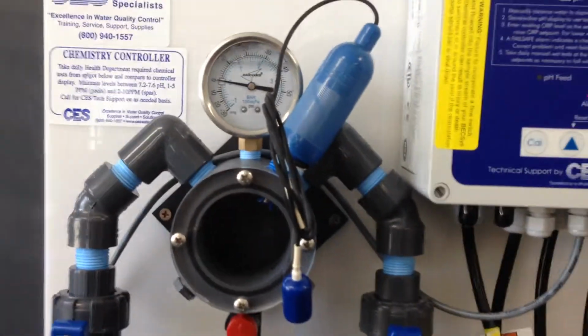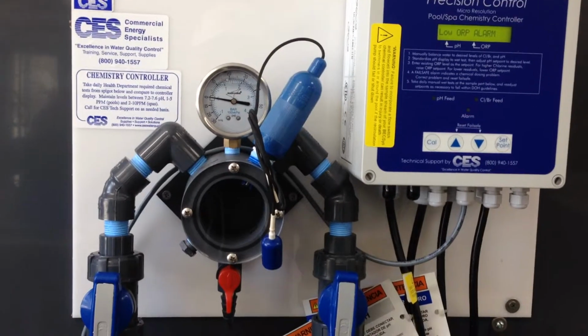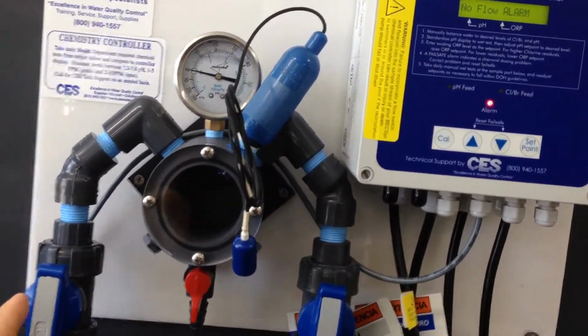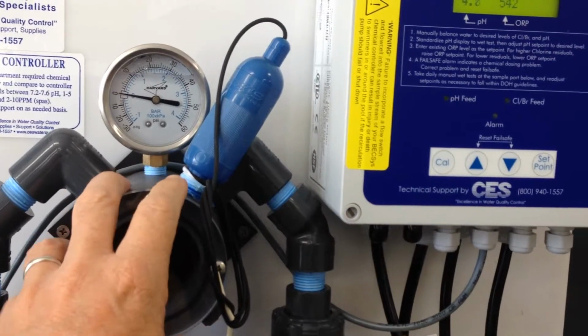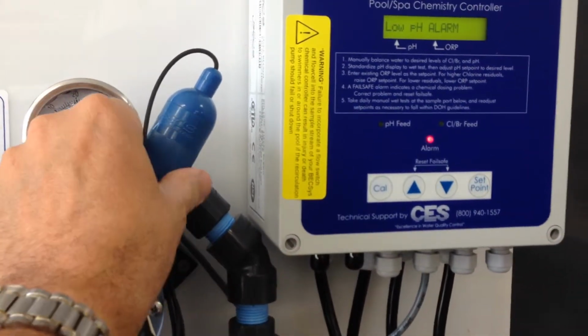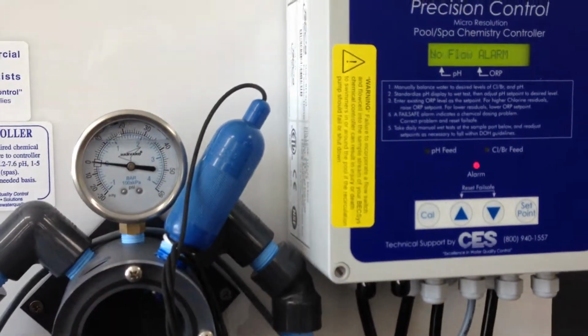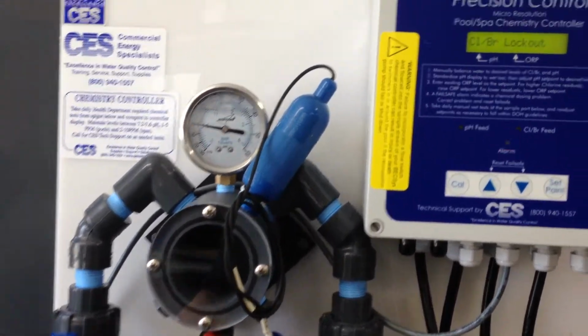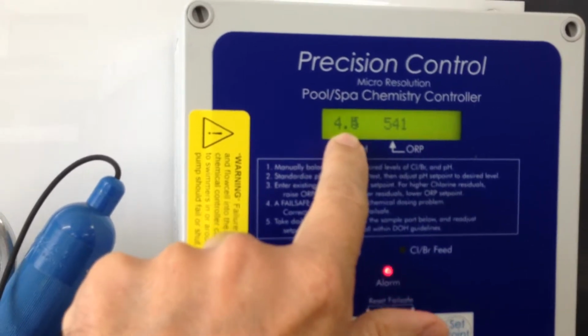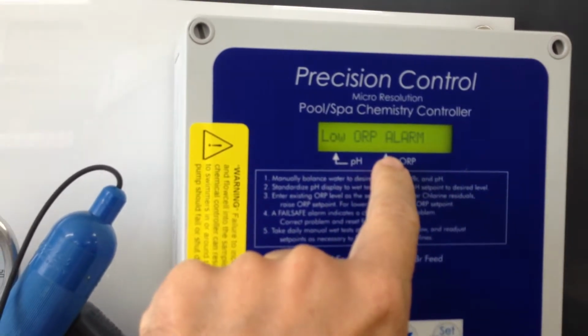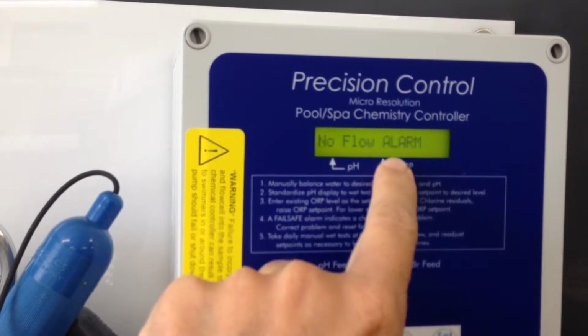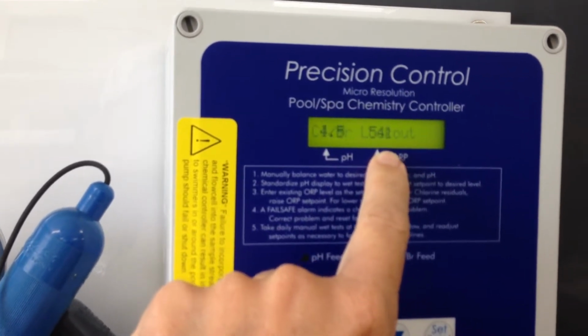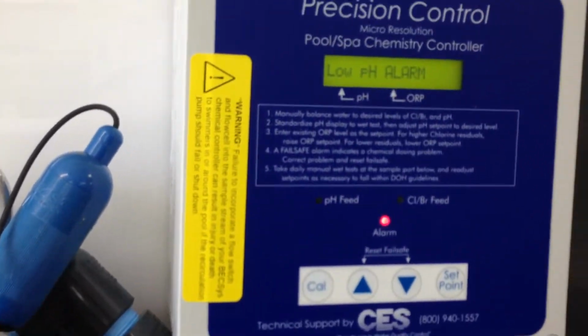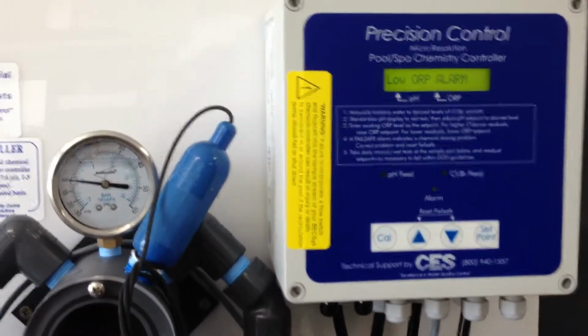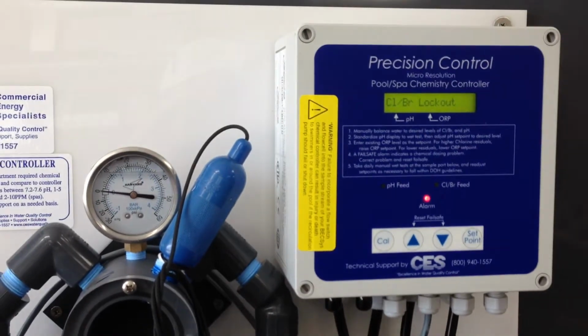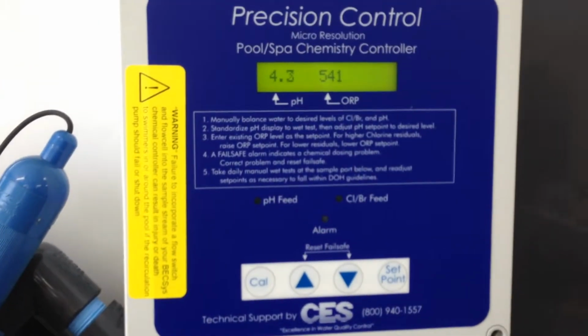Now these sensors will take a while to get used to the water, and so the way the system works is when the water passes by here, it reads the pH and it reads the kill power of the chlorine, which is in millivolts from 0 to 1,000. The pH is displayed on the reading, and the ORP is displayed on the reading as well. I'll wait till that comes up in a second. So when the set point is below where you want it to be, it feeds, and when it is above where it wants it to be, it shuts off. It's very simple to program.